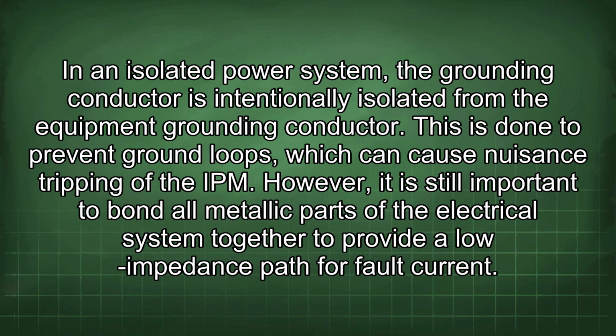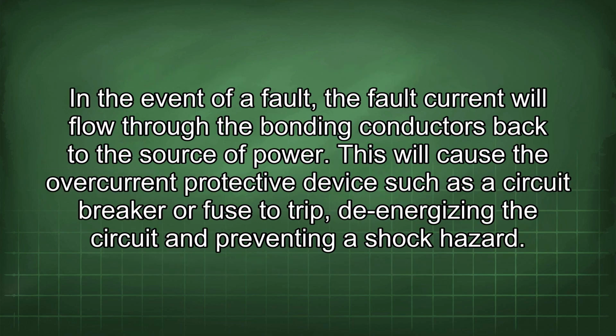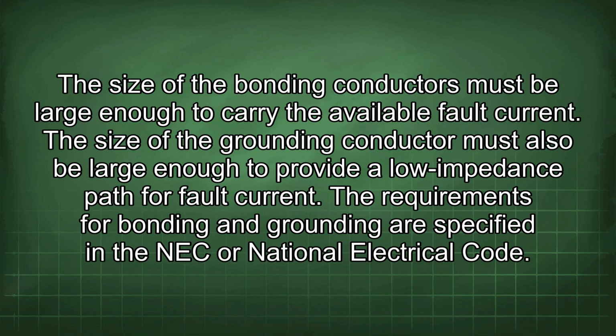This is done to prevent ground loops, which can cause nuisance tripping of the IPM. However, it is still important to bond all metallic parts of the electrical system together to provide a low impedance path for fault current. In the event of a fault, the fault current will flow through the bonding conductors back to the source of power. This will cause the overcurrent protective device such as a circuit breaker or fuse to trip, de-energizing the circuit and preventing a shock hazard. The size of the bonding conductors must be large enough to carry the available fault current. The size of the grounding conductor must also be large enough to provide a low impedance path for fault current.